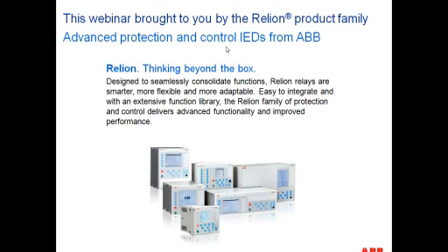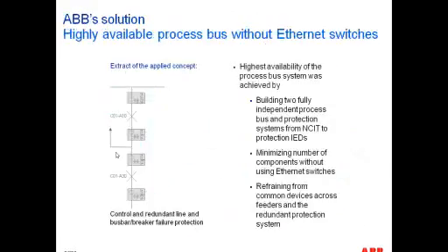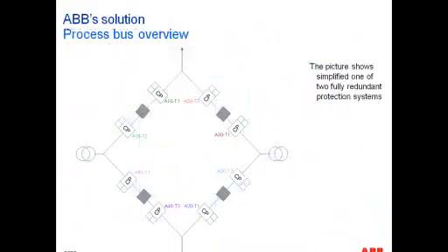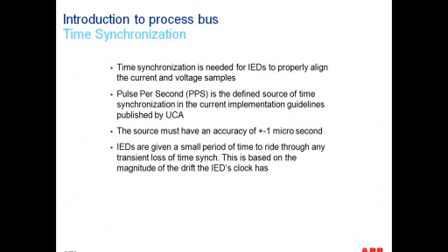Network congestion. Okay, so I have a question here that says, what happens when the allowable drift time expires? I think this question goes back to my comment about time synchronization, where I mentioned that the standard now defines a behavior if, for example, a merging unit loses its source of time synchronization. And there is a ride-through time, if we want to put it in those terms, once that happens.